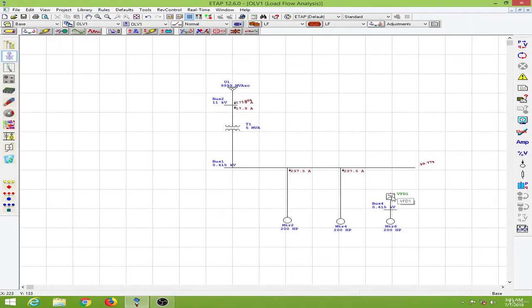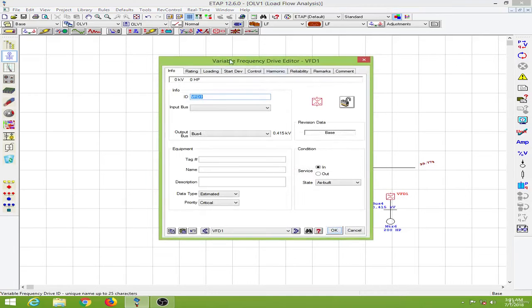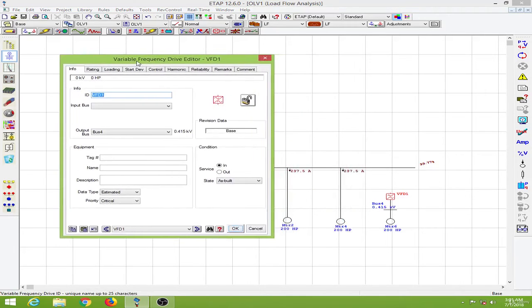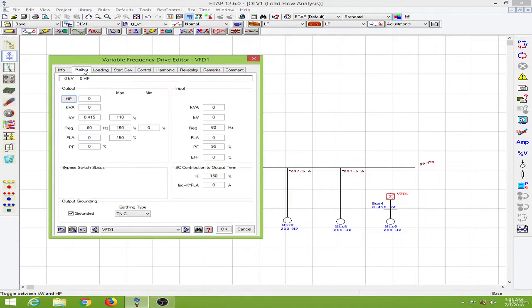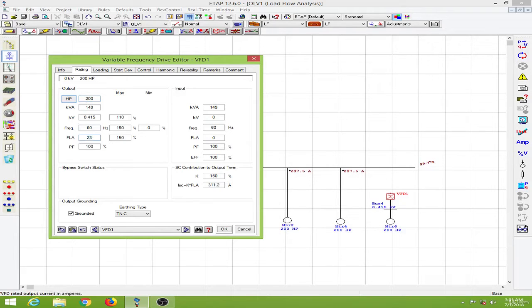Now let us edit the variable frequency drive. The variable frequency drive editor pops up and we will go to the ratings page. We know the hp rating of the motor is 200 hp, and the full load current is 237.5 amps, which we have from the load flow analysis.